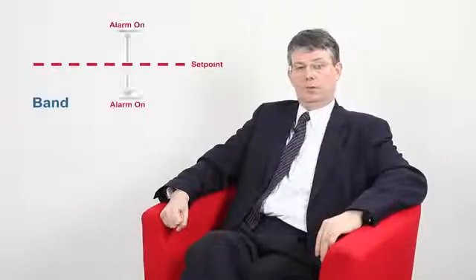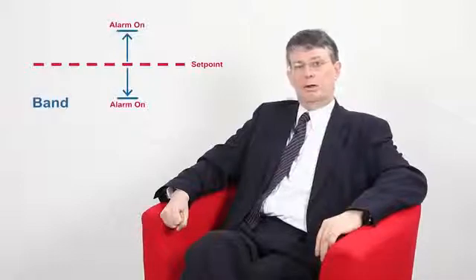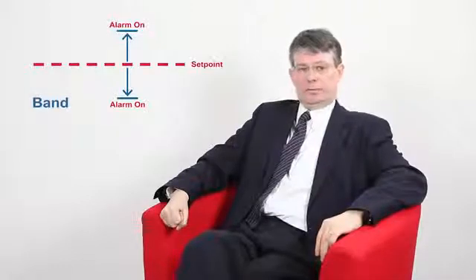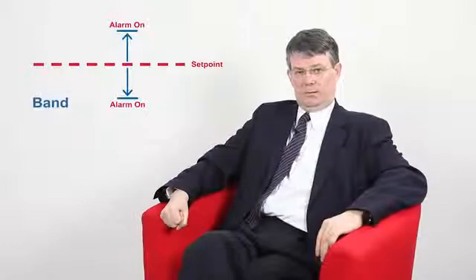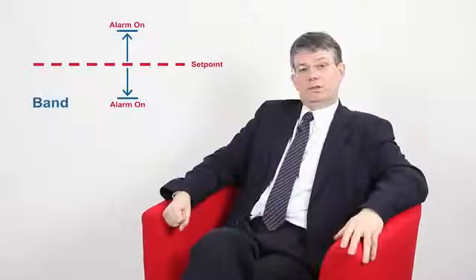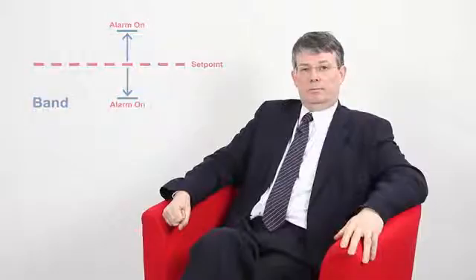However, if you want an alarm that is symmetrical around the set point — perhaps 5 degrees above and 5 degrees below — there is another option. This is the band alarm. You set a single alarm with a single value, and the alarm will activate if the process is that amount above or below the set point. The advantage of this is you use only one alarm and it is much simpler to set up.